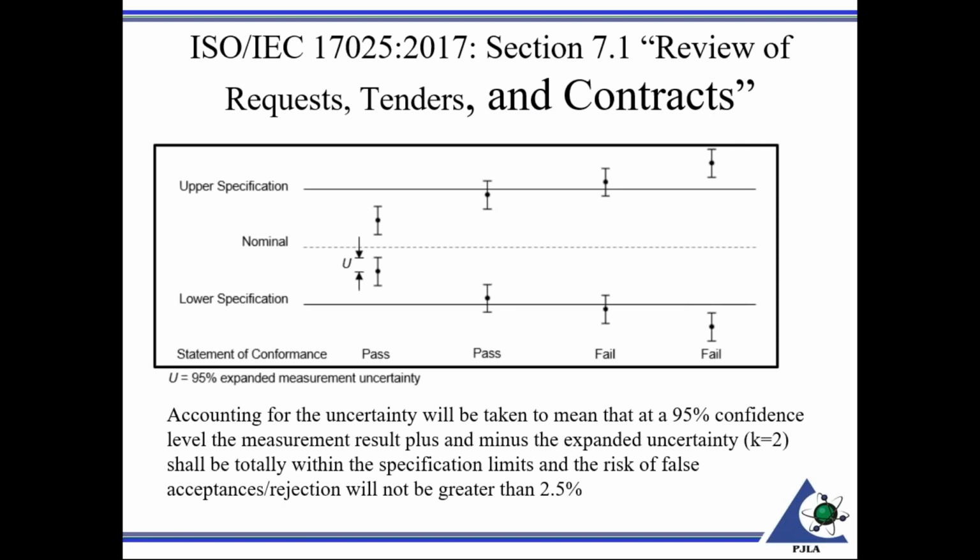That would be identified as perhaps an asterisk that would say taking uncertainty into account. In this particular example, it may actually produce an as found failure. Or before we revised our PL3, and you can still use that, we used to, not required, as guidance, you could specify this not as a clear pass or fail, or perhaps as a pass indeterminate in that particular case.